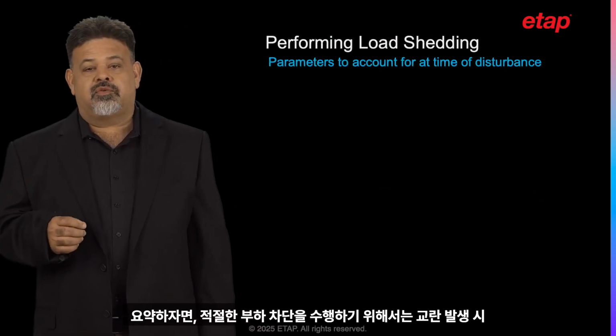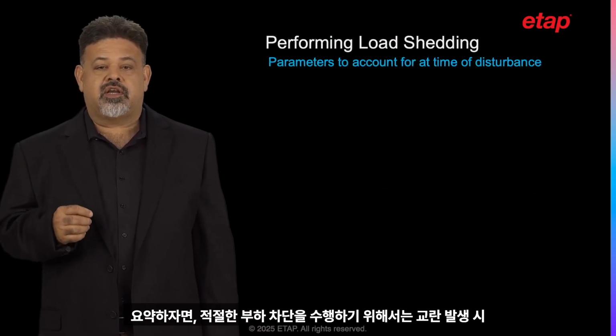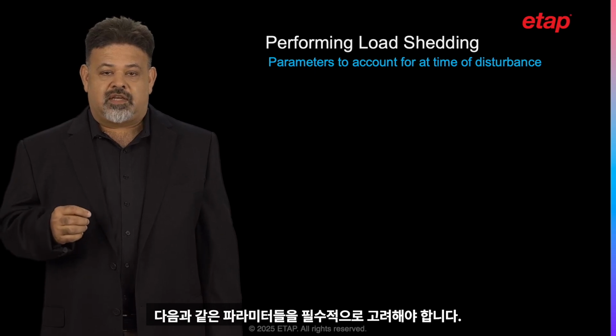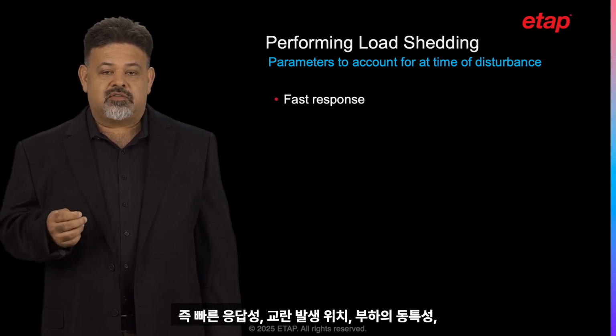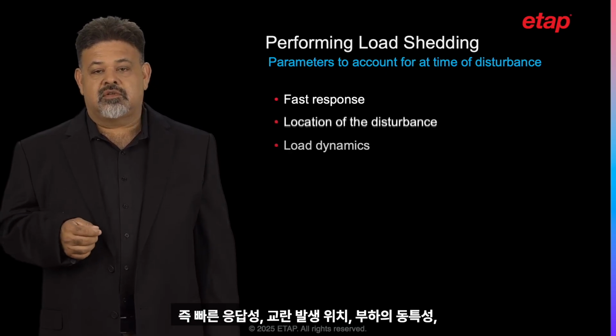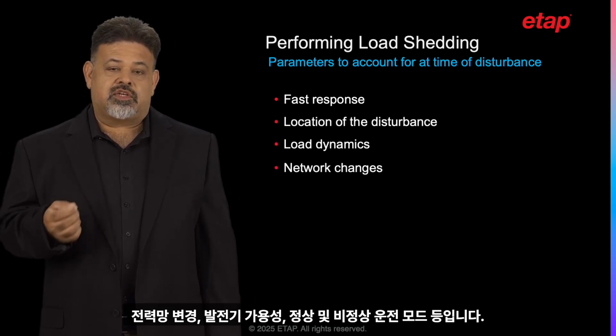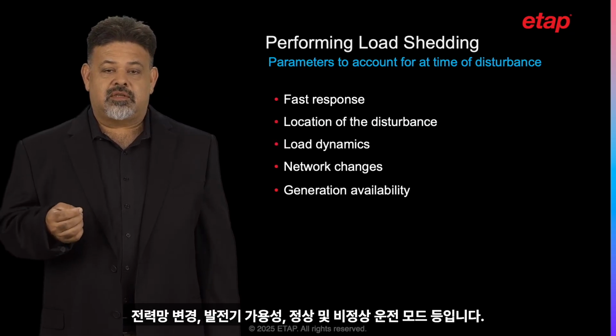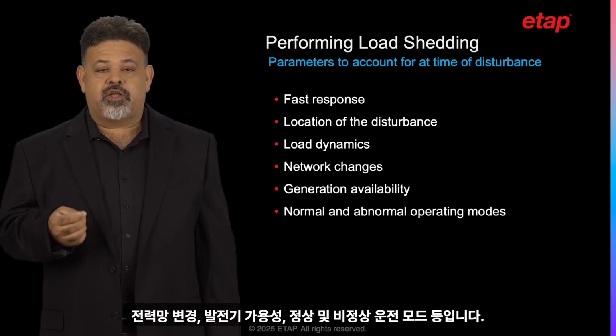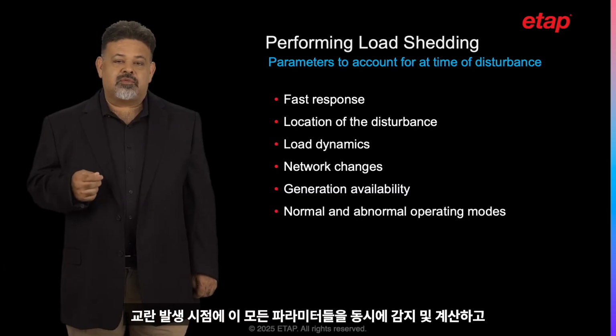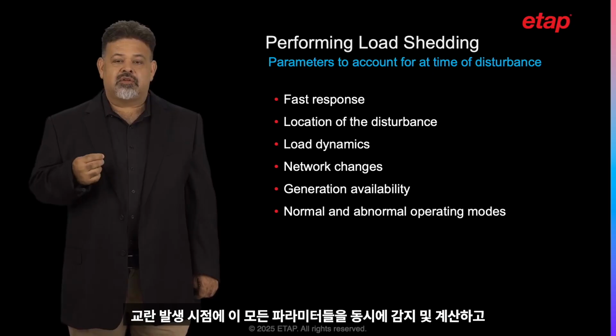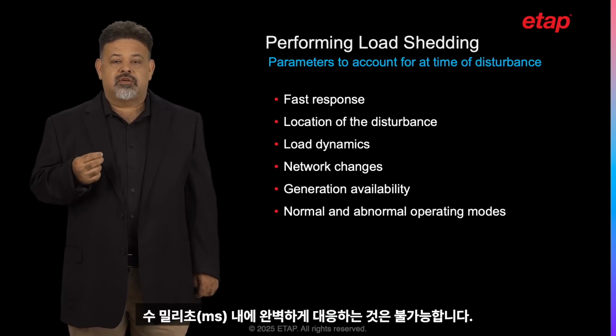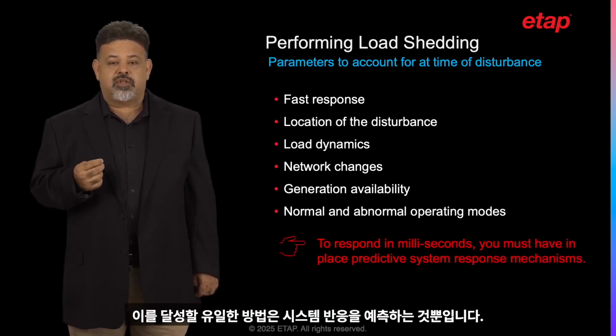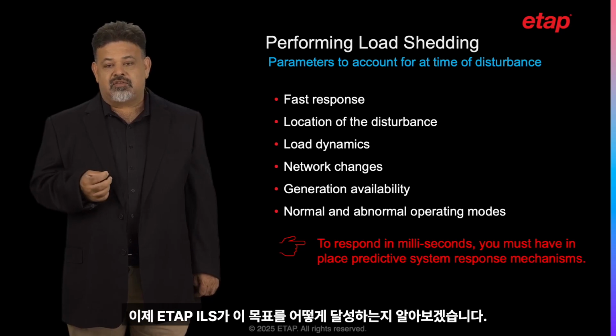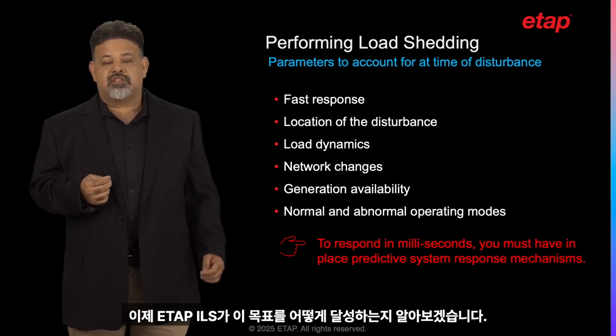In summary, to perform proper load shedding, it is essential to account for the following parameters at the time of the disturbance: fast response, location of the disturbance, load dynamics, network changes, generation availability, normal and abnormal operating modes. Since it is impossible to detect, calculate, and respond considering all these parameters at the same time of the disturbance and respond within milliseconds, the only method to achieve this is through predicting the system response. Next, let's discover how ETAP ILS can achieve this goal.